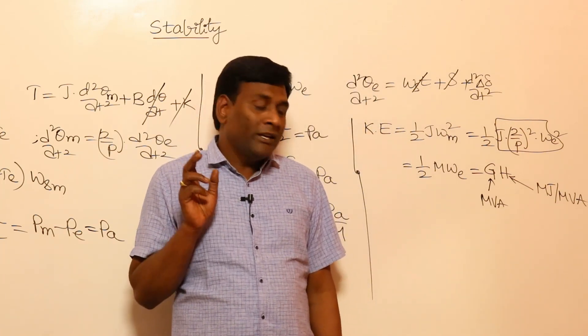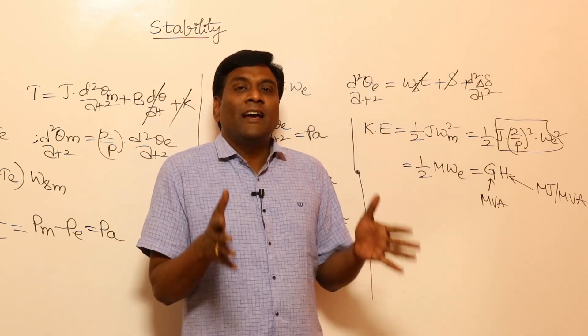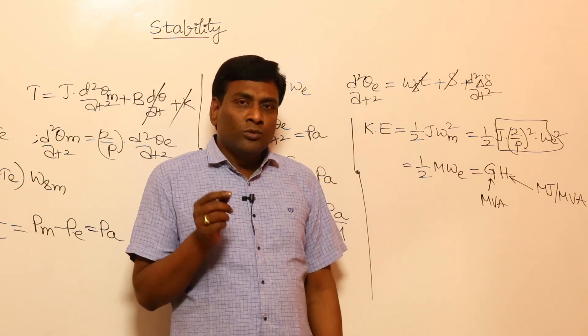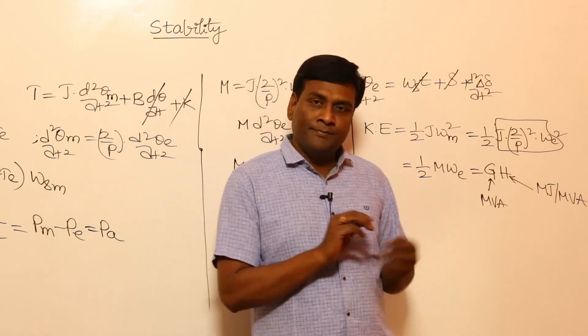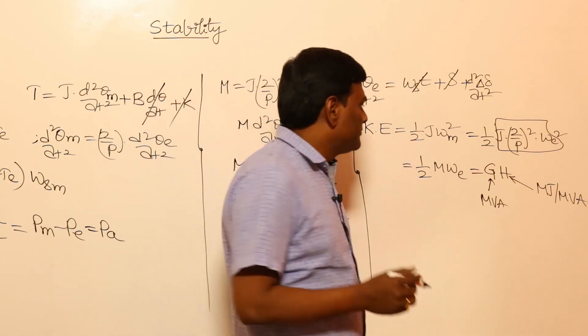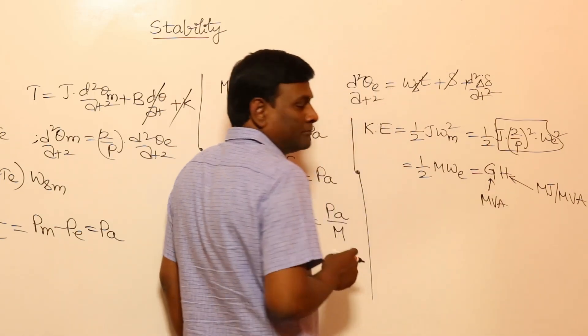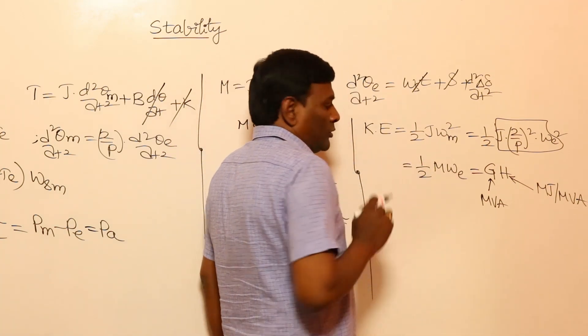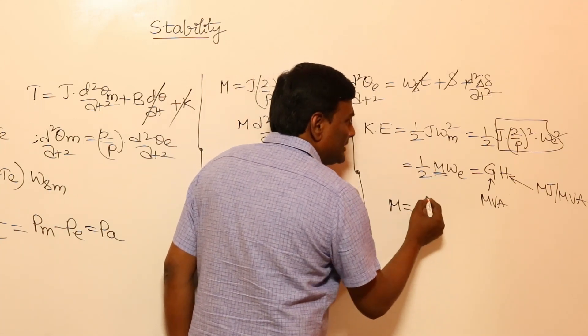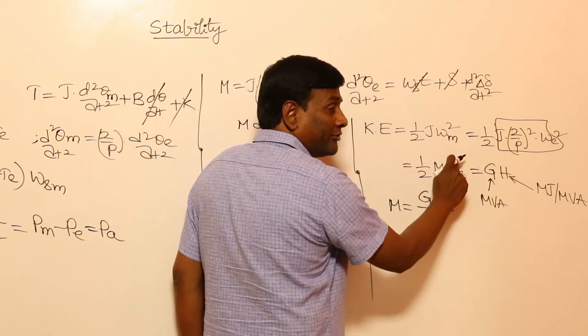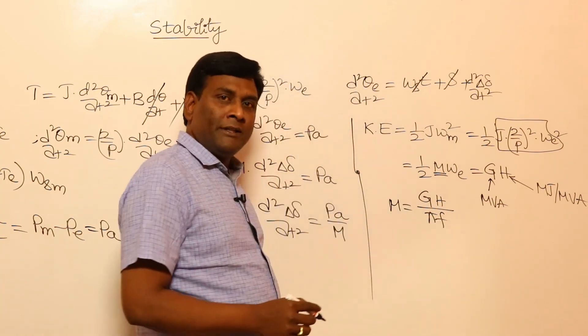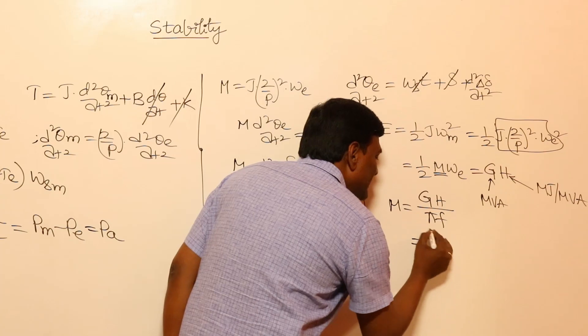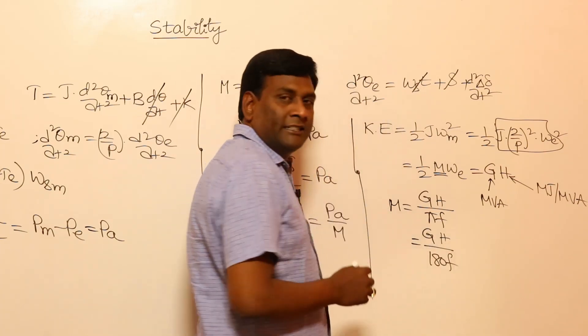For any given synchronous machine, the datasheet gives H — for example, 3 mega joules per MVA — representing how much kinetic energy is stored per MVA. Now M = G·H / (π·f) in electrical radians, or M = G·H / (180·f) in electrical degrees. Dimensions here are crucial for solving stability problems.